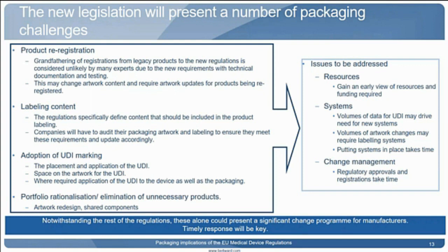The legislation brings in the requirements for UDI marking, and Mark is going to discuss that further in the next session. But what companies will have to do from a packaging perspective is obviously determine where on the packaging they're going to place the UDIs. They may need to create space on the artwork for the UDIs to be added. And in some cases, where it's a reprocessed medical device, the UDI will have to be applied to the device as well as the packaging. Because obviously when a device gets used, it gets separated from the packaging, and when it's reprocessed, you need to keep the chain of history of that device.